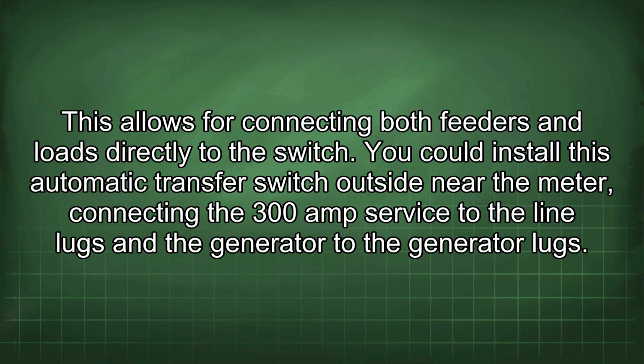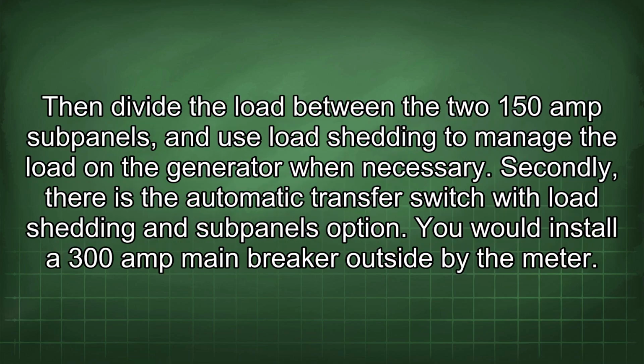You could install this automatic transfer switch outside near the meter, connecting the 300 amp service to the line lugs and the generator to the generator lugs. Then divide the load between the two 150 amp subpanels and use load shedding to manage the load on the generator when necessary. Secondly, there is the automatic transfer switch with load shedding and subpanels option.